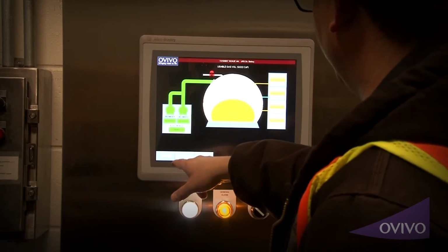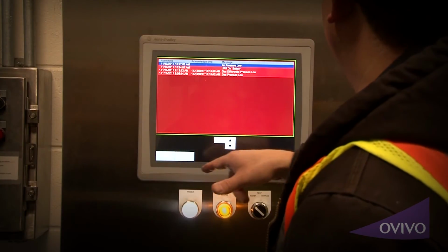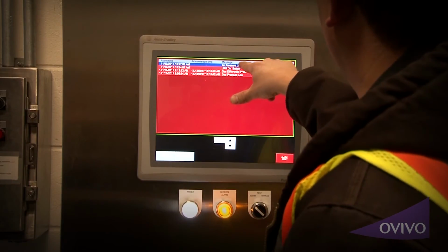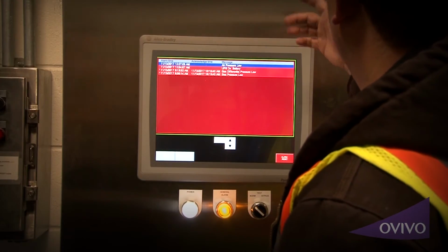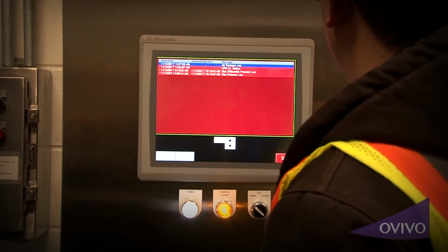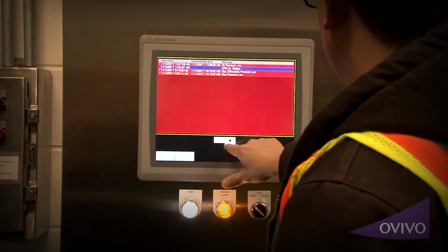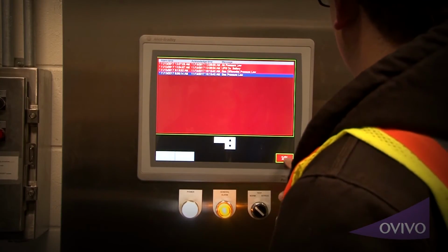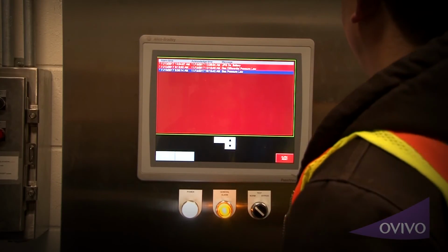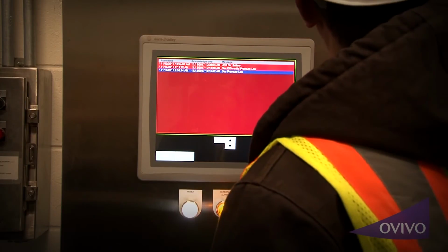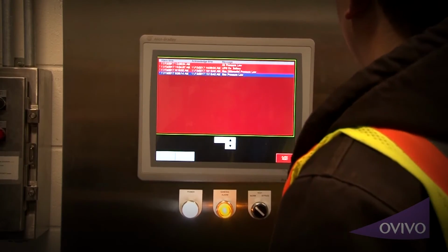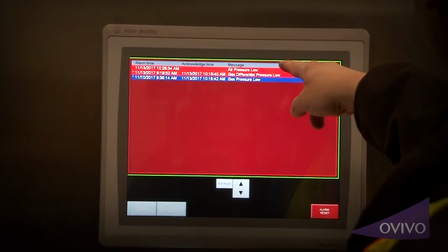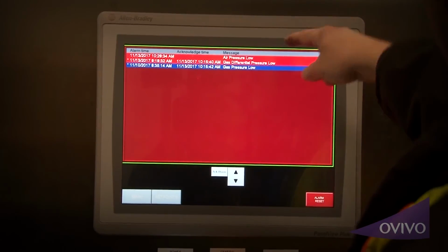And this right here, I'll bet there is a low air pressure alarm. There we go, UPS on battery, okay, because we opened it up, we shut it off. Air pressure low, so now both fans are on. Gas pressure differential and gas pressure low, those are all set. Acknowledge the alarms. Reset. UPS battery is still on. There we go. We were running off the UPS battery. UPS battery off, but the air pressure is still low.